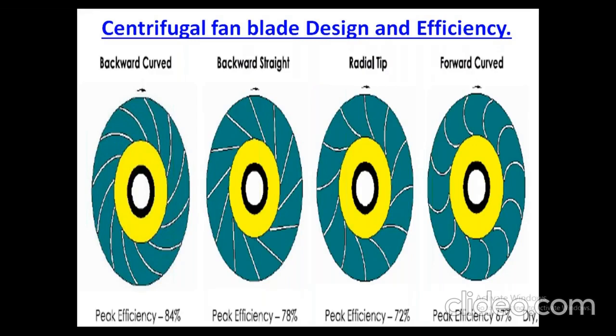When you go for an energy audit, you just look at the blowers, you visualize the blower internals. Ask them to open any of the blowers and see this, and ask them to change the impellers. Instead of a straight impeller, if they go for a curved impeller, they can straight away achieve the energy savings.